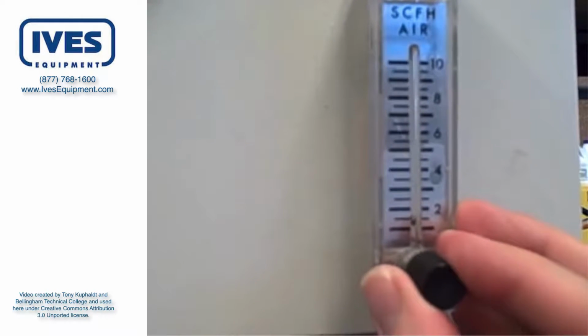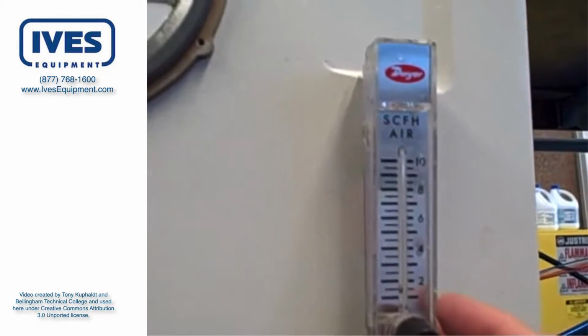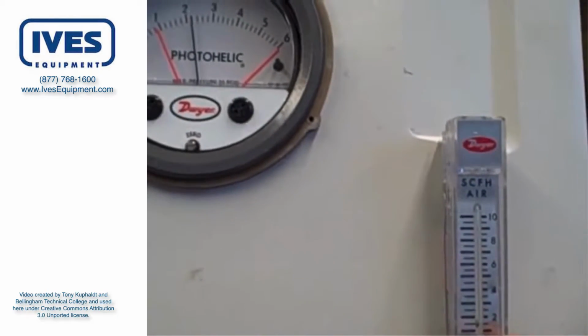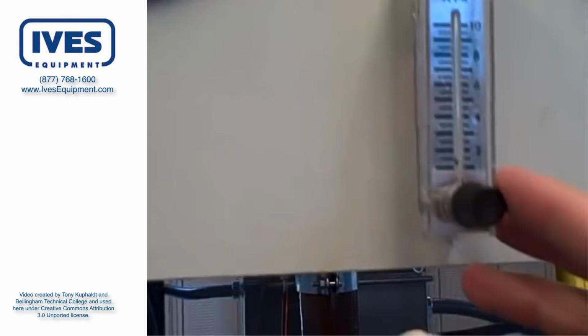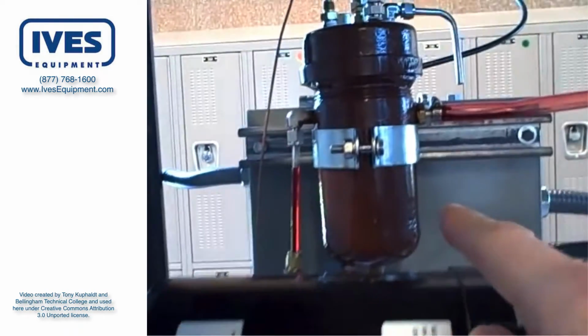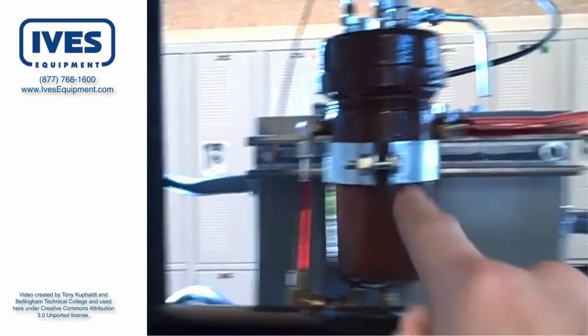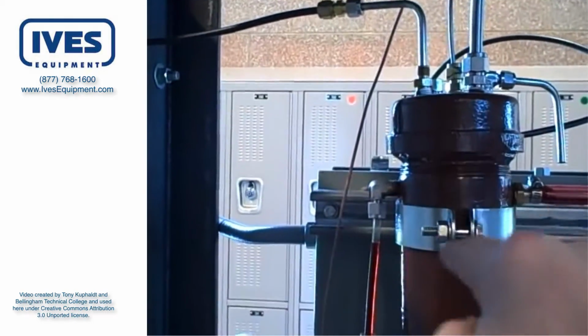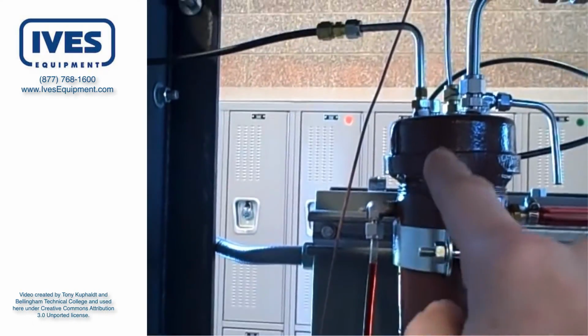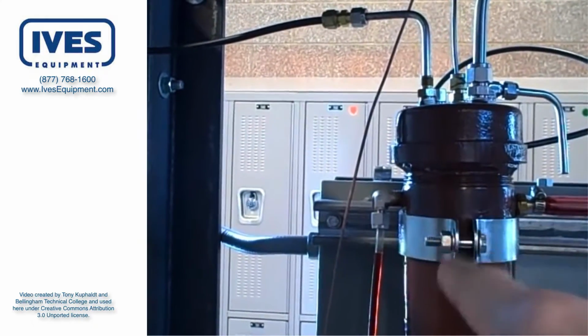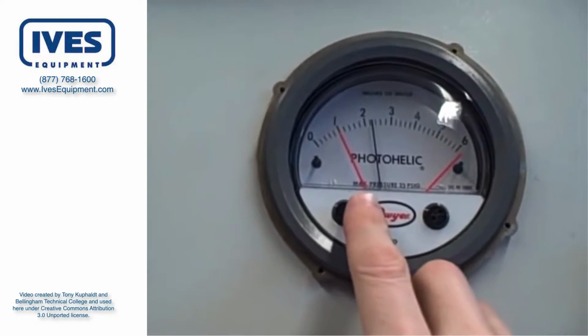This particular installation we're using the Flowmeter for is metering airflow into a bubble tube to measure the level of oil inside of a reservoir. There's our oil reservoir right here. It's lubricating oil for our turbo compressor system, and we have a bubble tube going into it that's bubbling air through it. We use the back pressure in that bubble tube to monitor the height or level of oil in the reservoir, and that pressure is monitored by this Photohelic gauge.